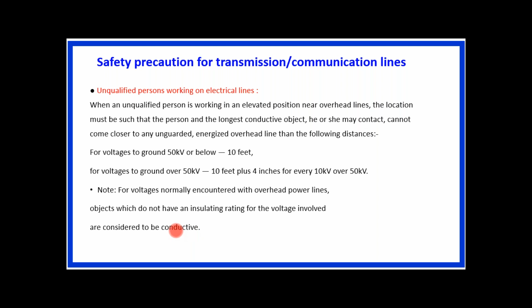And for the qualified persons working on the electrical lines, the guidelines are given again. When a qualified person is working in the vicinity of overhead lines, whether in an elevated position or on the ground, the person may not approach or take any conductive object without an approved insulating handle closer to exposed energized parts unless the person is insulated from the energized part. So the person should be insulated from the energized part. That insulation may be through gloves, with sleeves if necessary, rated for the voltages involved, and is considered insulation of the person from the energized part on which work is performed.